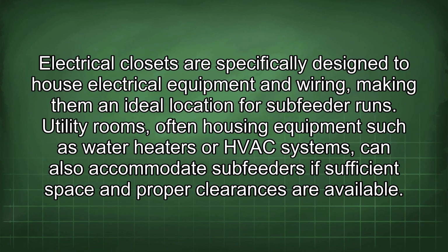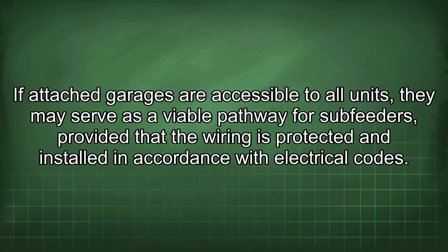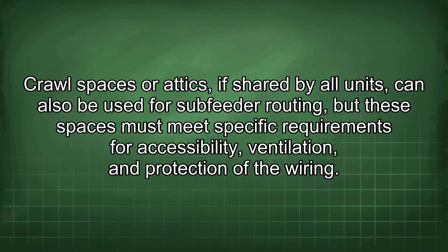Electrical closets are specifically designed to house electrical equipment and wiring, making them an ideal location for subfeeder runs. Utility rooms, often housing equipment such as water heaters or HVAC systems, can also accommodate subfeeders if sufficient space and proper clearances are available. If attached garages are accessible to all units, they may serve as a viable pathway for subfeeders, provided that the wiring is protected and installed in accordance with electrical codes. Crawl spaces or attics, if shared by all units, can also be used for subfeeder routing, but these spaces must meet specific requirements for accessibility, ventilation, and protection of the wiring.